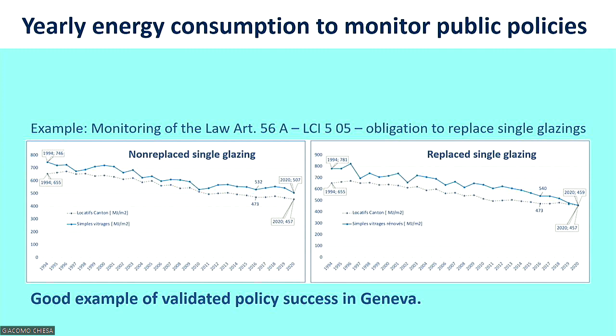this is strategic for Geneva. They were at 600 megajoules per square meter of consumption, as the previous regulations already did, but now they are at 450. So now 450 is the target that every building in Geneva, and this is inside the regulation, should not exceed. If you exceed 450, then it is imposed that you apply optimization, because the optimized buildings are better than 450.